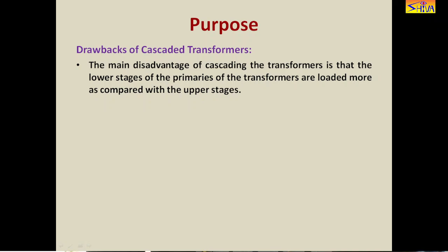The first drawback was that the lower stages of the primaries of the transformers are loaded more as compared with the upper stages. The reason is the first stage is supplying the excitation for the second stage as well as the third stage. The second drawback is that large excitation current is required because all the excitation current is supplied by the first stage — the second and third stages' excitation current requirements are all fed through the first stage.